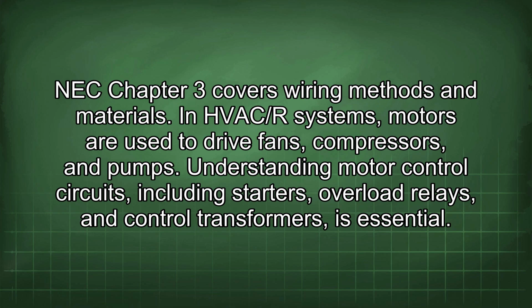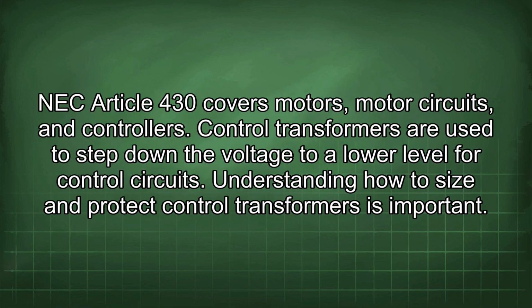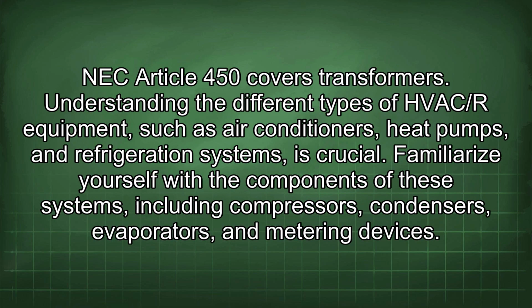In HVAC/R systems, motors are used to drive fans, compressors, and pumps. Understanding motor control circuits, including starters, overload relays, and control transformers, is essential. NEC Article 430 covers motors, motor circuits, and controllers. Control transformers are used to step down the voltage to a low level for control circuits. Understanding how to size and protect control transformers is important. NEC Article 450 covers transformers.